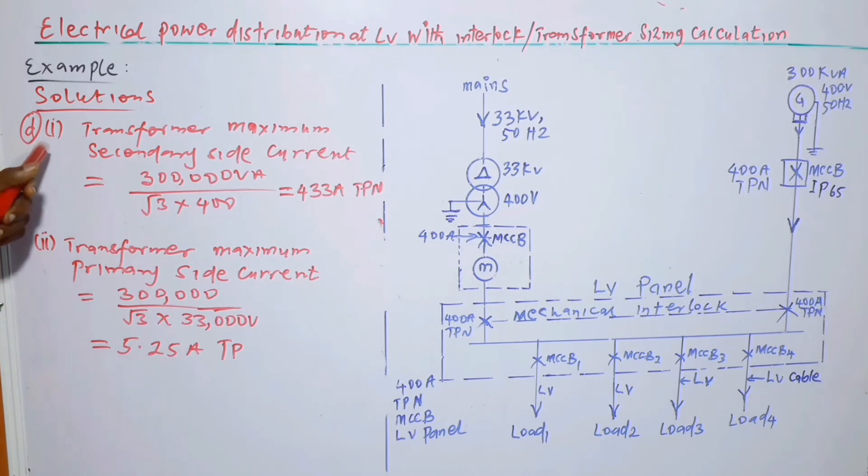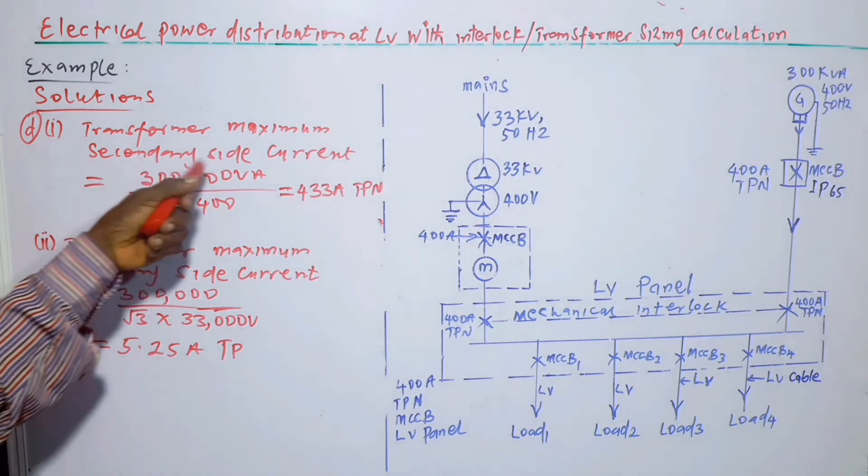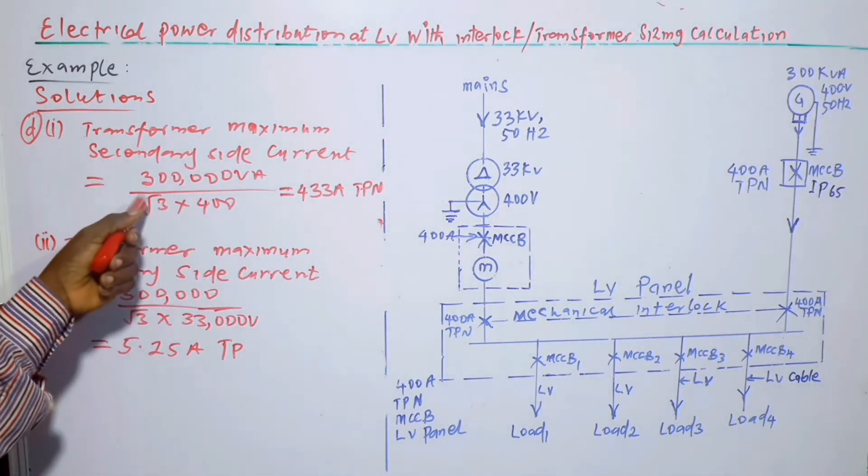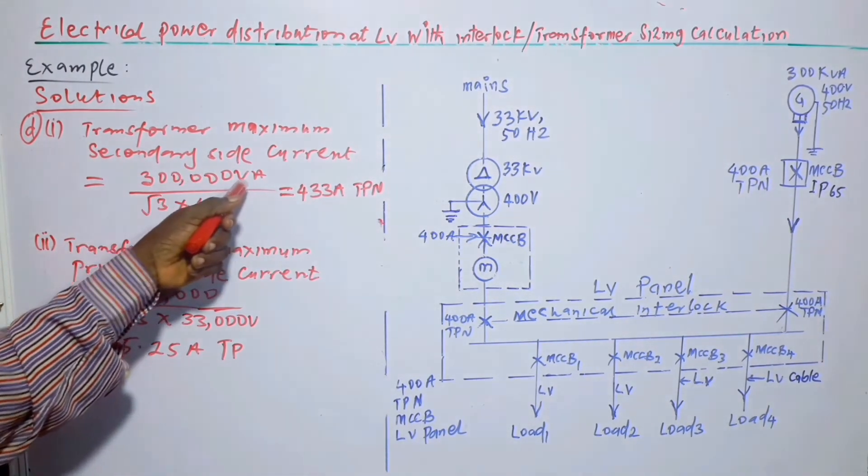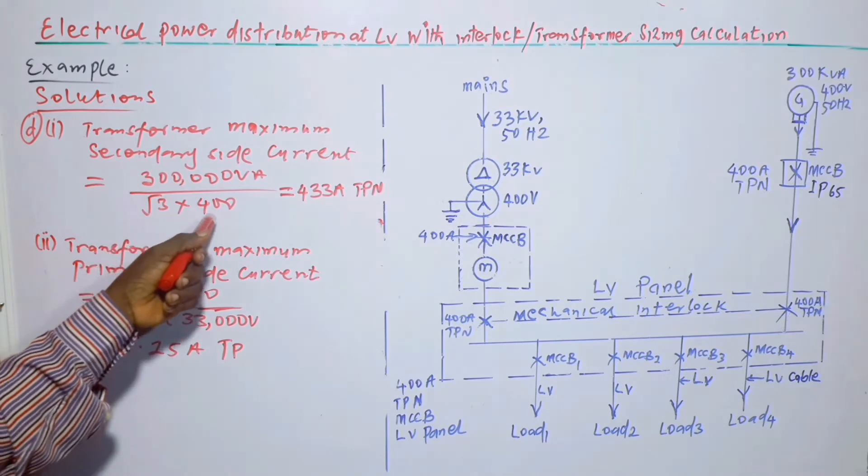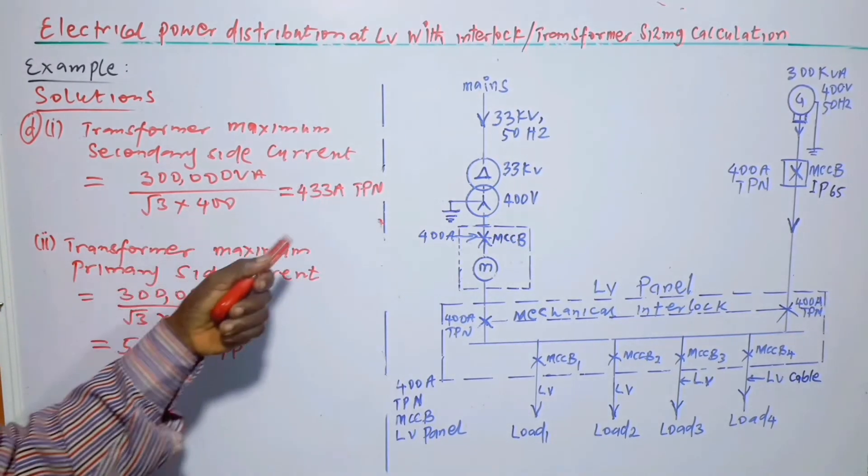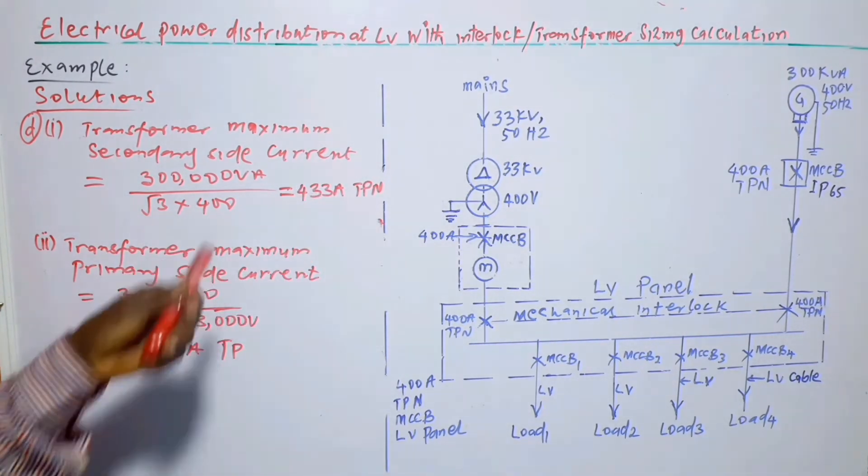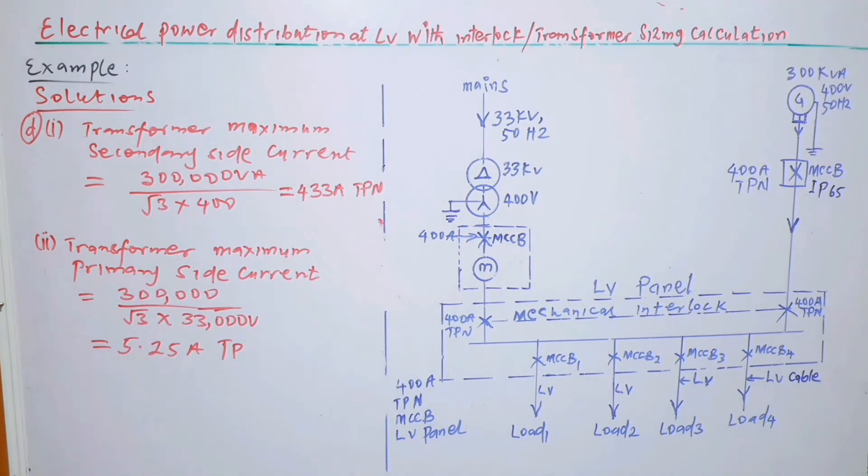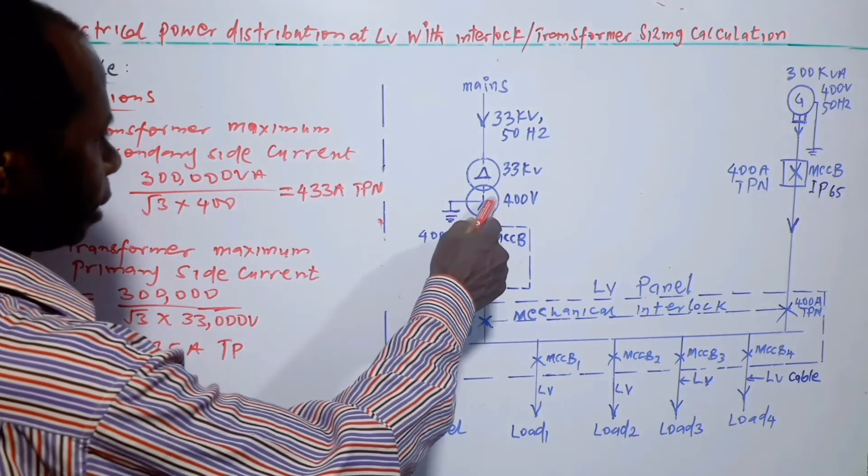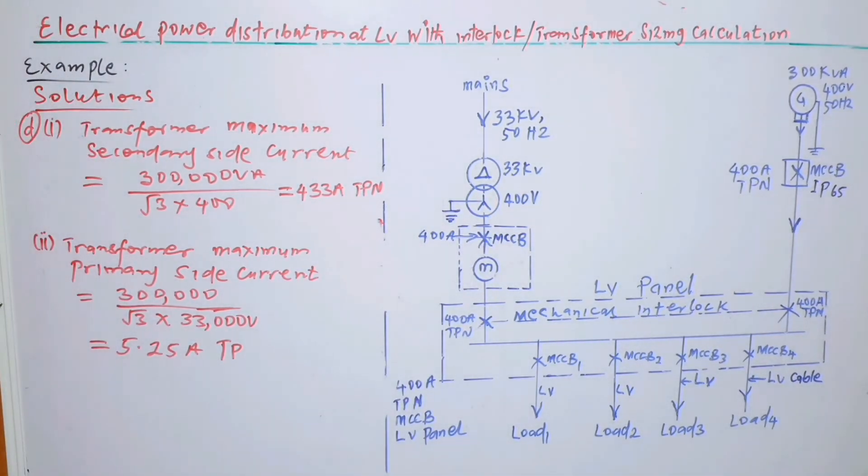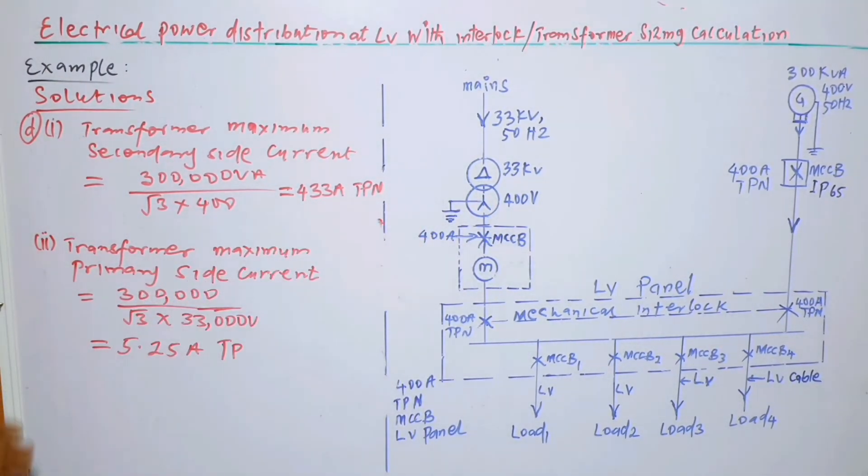One can move a step further by having the D part. D part one: Transformer maximum secondary side current is equal to 300,000 VA divided by root 3 times 400. And the answer is 433 TPN. We are talking of this star side, that's the secondary side.